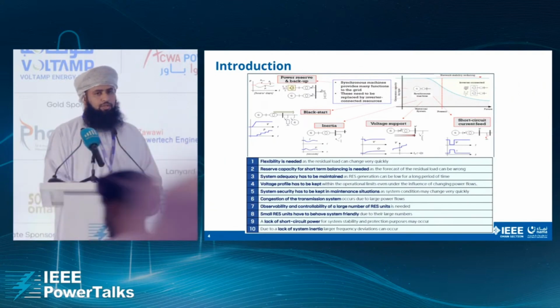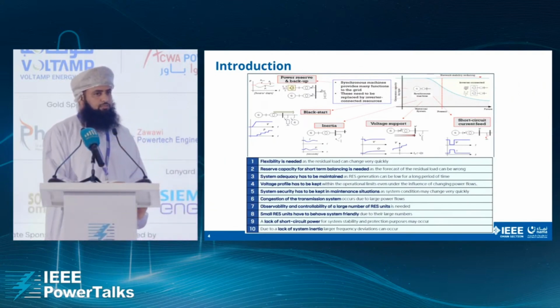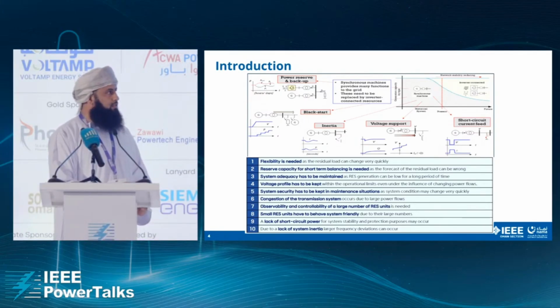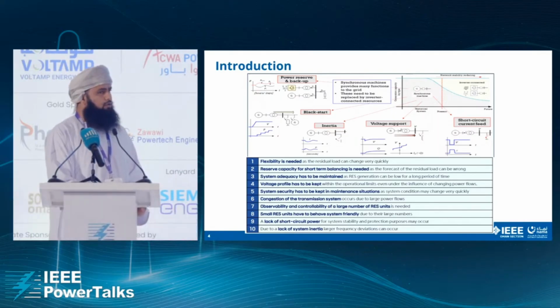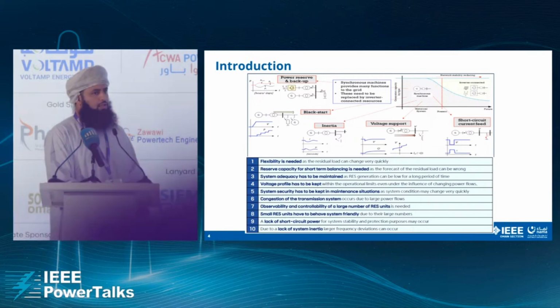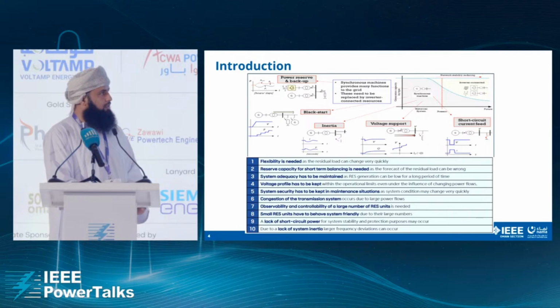Having a lot of renewable energy integration into the transmission system will introduce challenges in terms of voltage support, frequency support, short circuit level in the transmission system, and also a reduction in inertia. All of that will have an impact on voltage stability and frequency stability, where reducing the inertia in the system by replacing the existing conventional machines with renewable energy will decrease the inertia and increase the rate of change of frequency in the system.